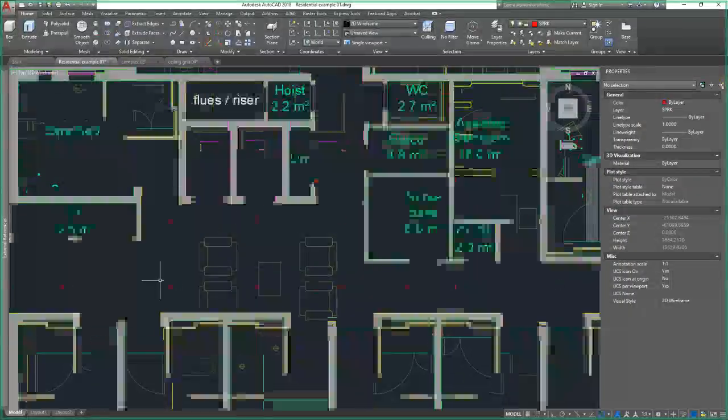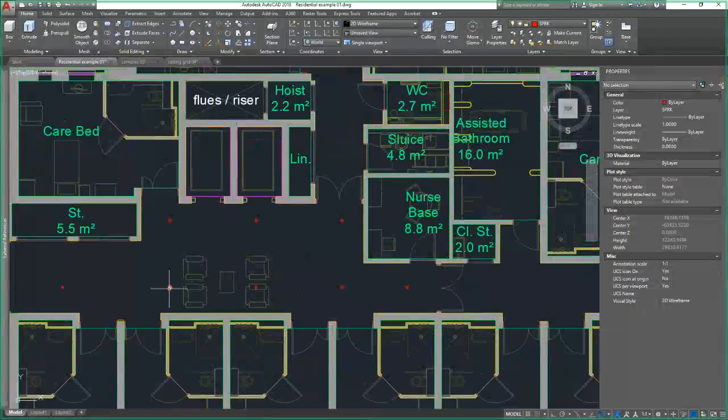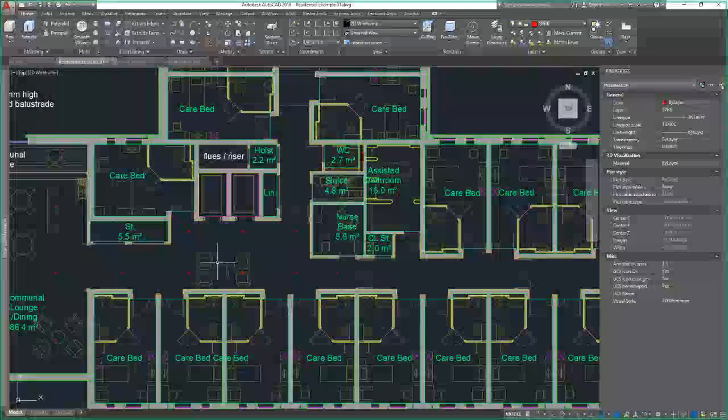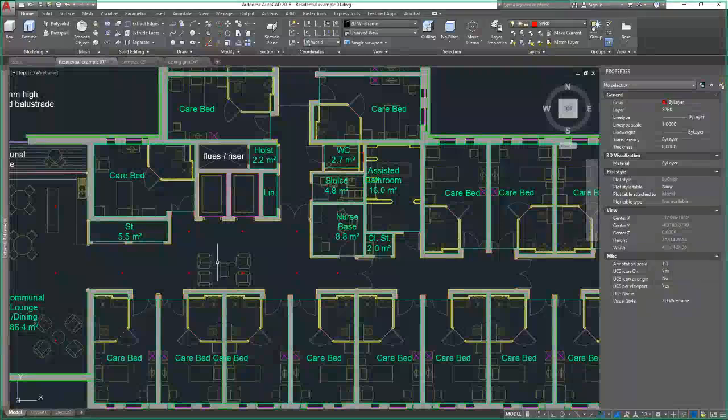I made this distance a little bit bigger so that I can then put 6 heads within this area here, which all look nice, look neat in neat rows and even spacing. Again, that's the aim of the game. And yes, we need to make the sprinkler heads compliant, but it's got to look right. We've got to use straight lines where we can.